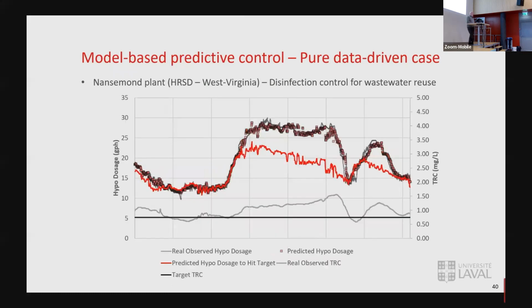Here it's different - this is another day. The model would have done the same thing, and the red boxes are very close to the gray data, but the result is not good - you're just overdosing this chlorine, coming in at way too high concentration. So the model would have gone with the red line, the model-based controller, which you can implement, and basically save chemicals or make sure that it's always good.